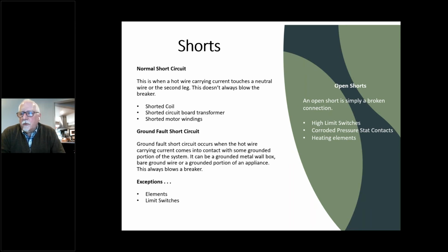You can even get shorted motor windings. For example, on a grinder you've got a start circuit and a run circuit. That start circuit may be fried, and the motor will spin if you spin it up, but the short circuit itself has disabled it. Whereas a ground fault short is where one of those wires has actually touched the frame of the machine somewhere, and a ground fault short will generally throw a circuit breaker. An open short is simply a disconnected wire. For example, you've got a high limit switch that's failed and the heating element won't come on. That's an open short because it's not doing its job.